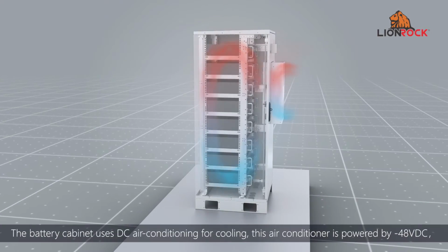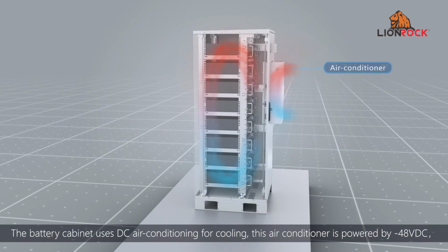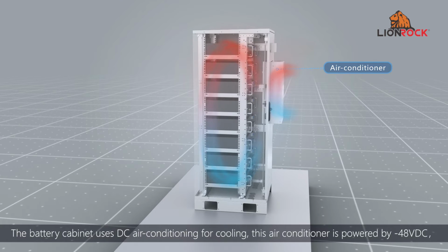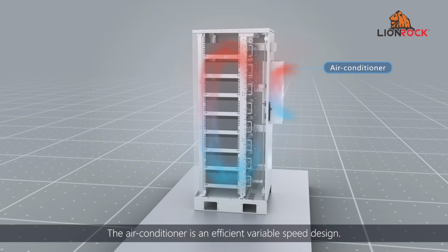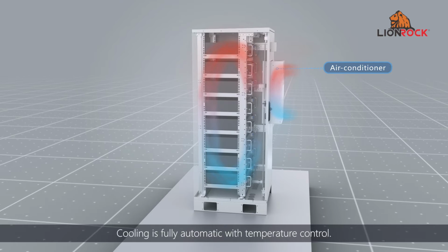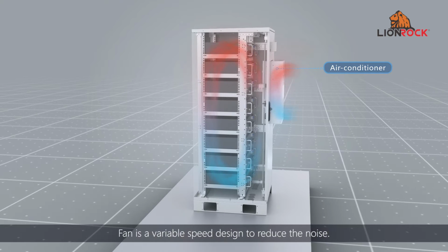The battery cabinet uses DC air conditioning for cooling. This air conditioner is powered by minus 48 volt DC. The air conditioner is an efficient variable speed design. Cooling is fully automatic with temperature control. The fan is a variable speed design to reduce the noise.